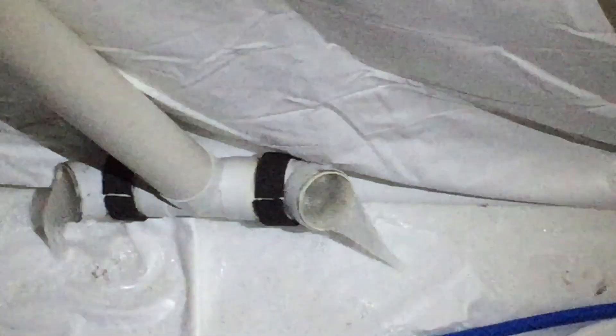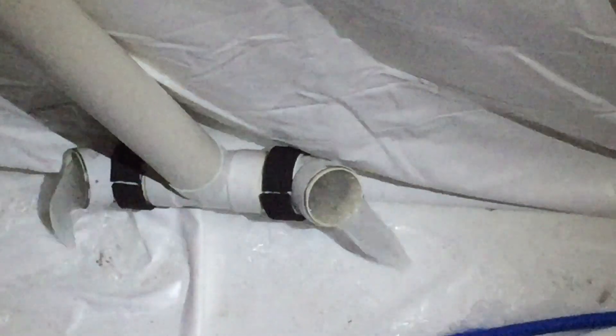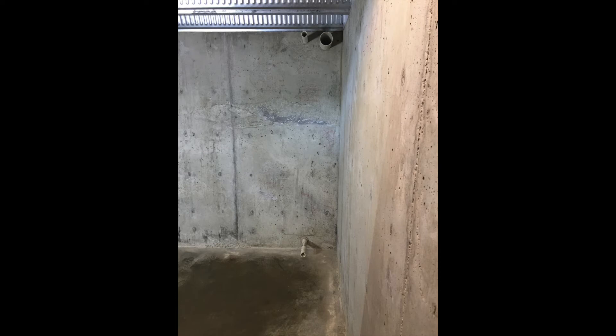What you see there is called a calming inlet. The way you want to pump the water into the cistern is you want it to go down near the bottom and reverse the flow so that it comes up near the bottom. This keeps from disturbing sediment on the bottom of the tank and keeps you from disturbing anything floating on the top.